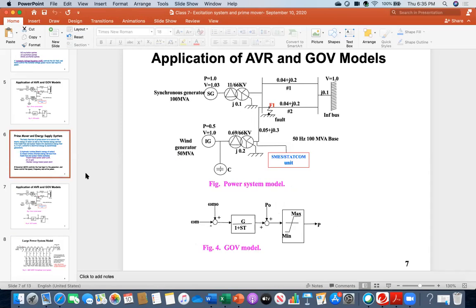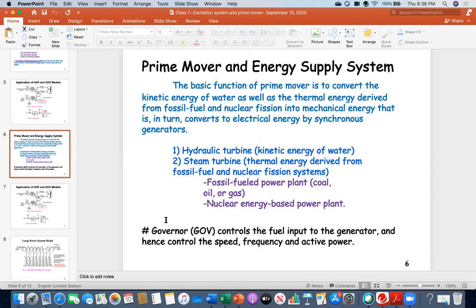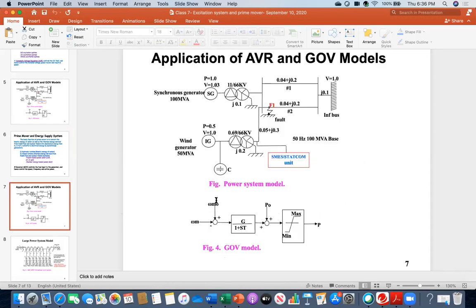We learned that your governor system controls the speed, frequency, and active power. That's why in the governor model, instead of voltage, here it is speed. This is your measured speed and this is your reference speed. For example, for the synchronous machine, your reference speed is 3000 RPM or 3600 RPM, or if it is hydraulic based, 1800 RPM or 900 RPM. During fault condition or any time, 24 hours, what is your measured speed, what speed you are actually getting on the shaft system, that speed will come here. If there is any difference, that will be processed through that low pass filter type.